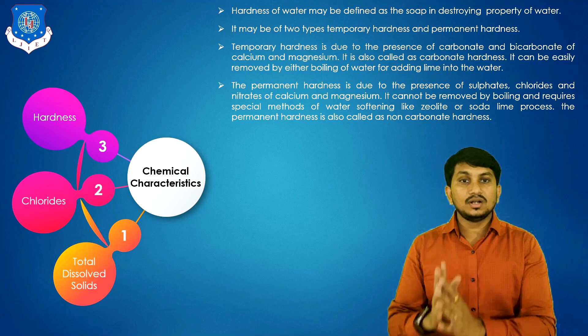The permanent hardness is due to the presence of sulfates, chlorides, and nitrates of calcium and magnesium. It cannot be removed by boiling and requires special methods of water softening like the zeolite or soda lime process. The permanent hardness is also called non-carbonate hardness. Hardness is measured in milligram per liter of calcium carbonate. The EDTA method is mainly used to measure the hardness of the water.